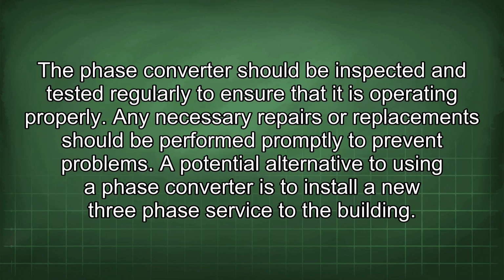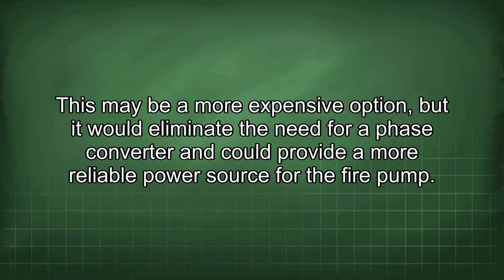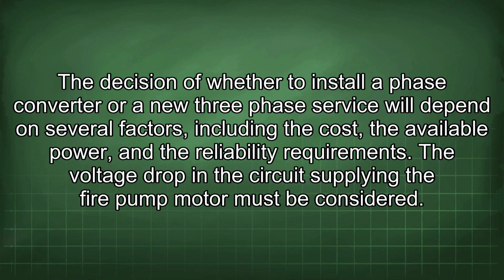The phase converter should be inspected and tested regularly to ensure that it is operating properly. Any necessary repairs or replacement should be performed promptly to prevent problems. A potential alternative to using a phase converter is to install a new three-phase service to the building. This may be a more expensive option, but it would eliminate the need for a phase converter and could provide a more reliable power source for the fire pump. The decision of whether to install a phase converter or a new three-phase service will depend on several factors, including the cost, the available power, and the reliability requirements.